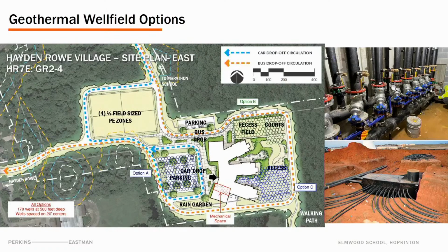Yeah, so what we're showing here is there are individual circuits, so each well isn't fed individually, they're in groups. So we would have, say, 17 circuits of 10 to get to 170. If there was a leak, we'd be able to tell from the pressures within the circuits which circuit the leak was in, and we could isolate that circuit. The building would still function. I'm not going to have to shut the whole building down because one circuit is off, and we'd have to go out and do some leak detection, which is not the easiest thing in the world to find water leaking in a pipe underground. But it's just like domestic water piping at this point. There's a way to go find that through sonar or.